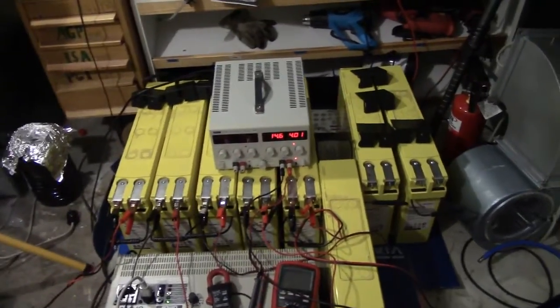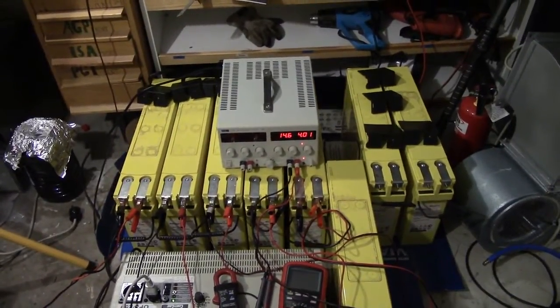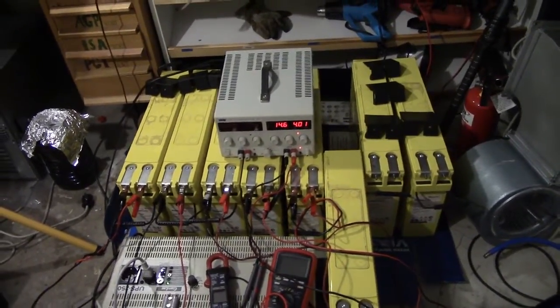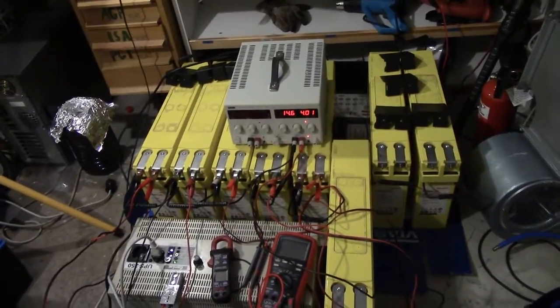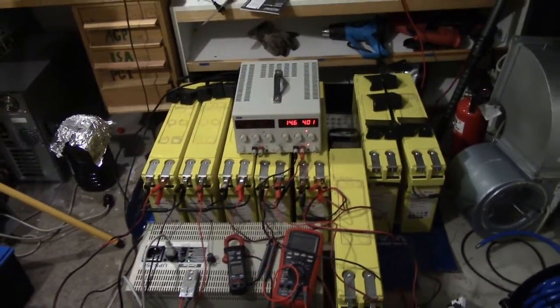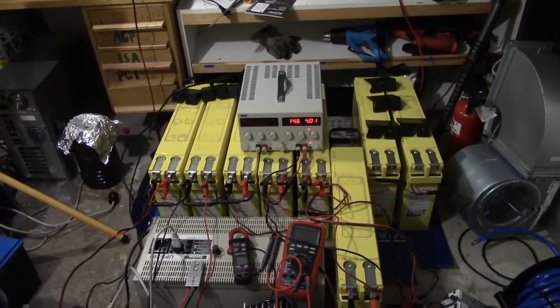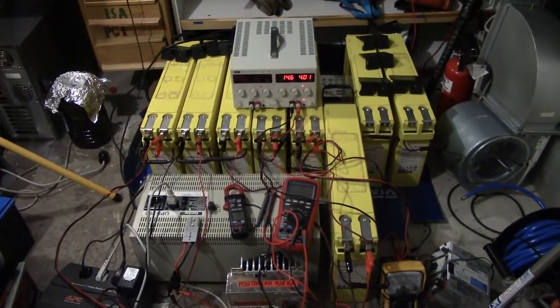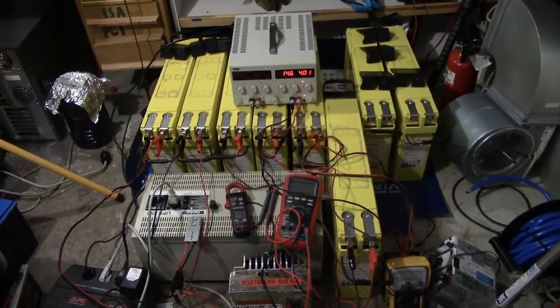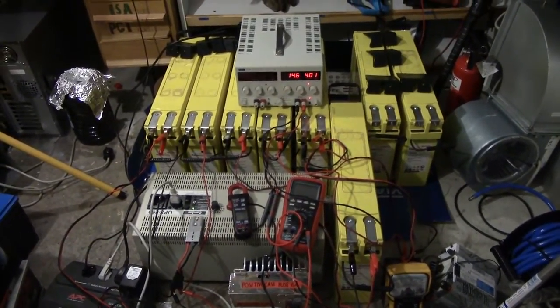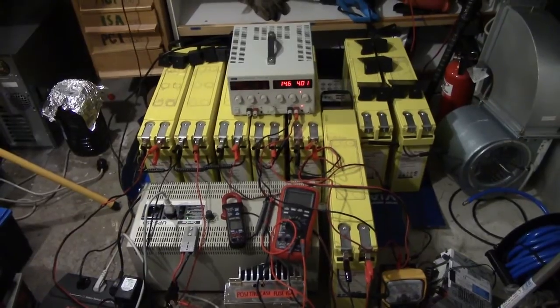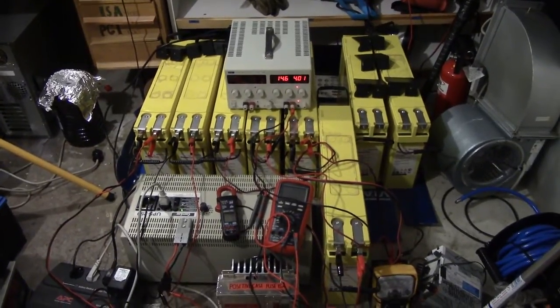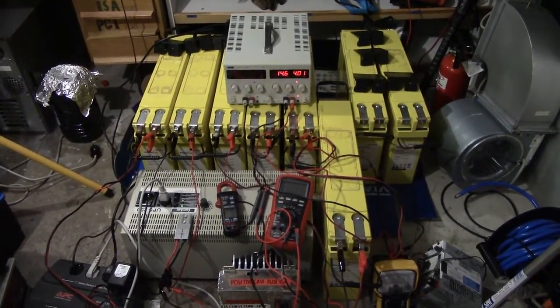This is confirmed by the fact that there have been several extended power outages lately so these batteries have been up to performance because else they would have been replaced due to poor performance rather than old age. They were surprisingly discharged when I got them but that could be due to the power outages just haven't given the battery management system enough time to recharge them fully. It's been just a couple of days since the last power outage when they were taken out of service.